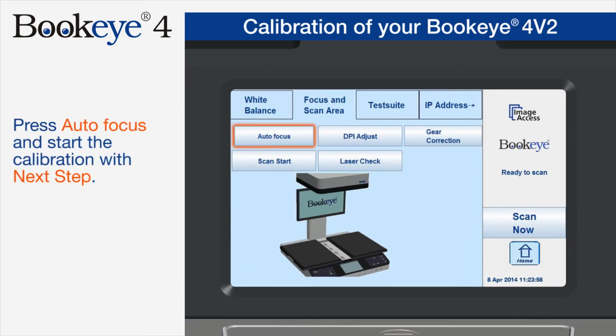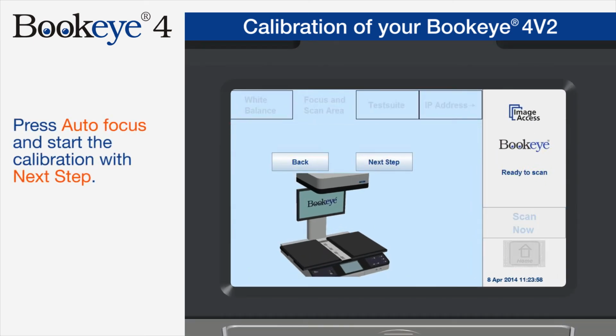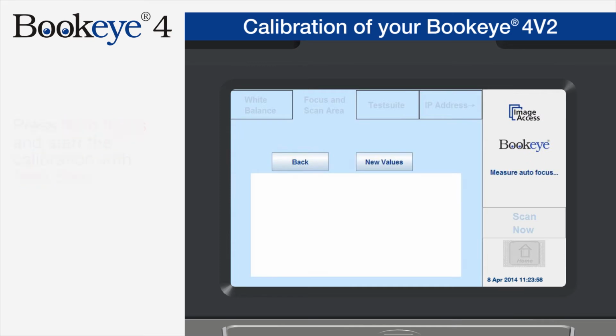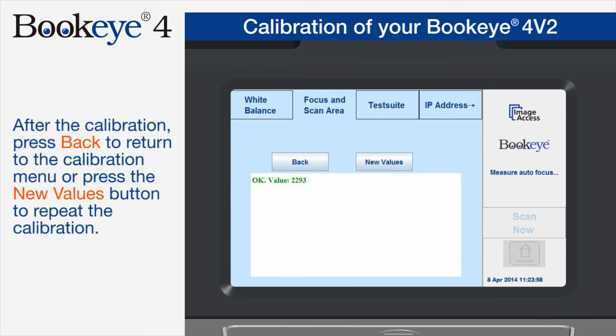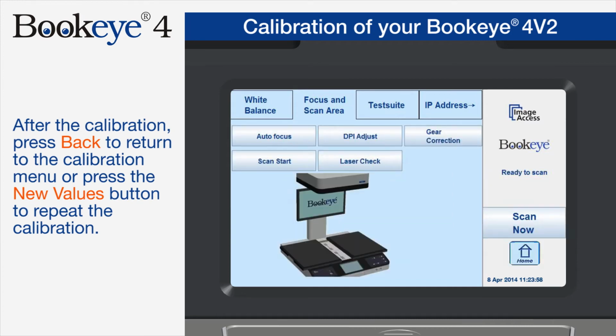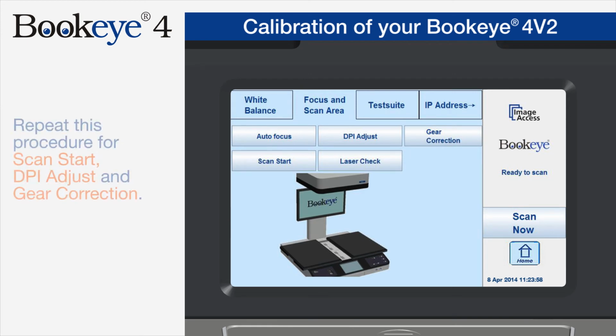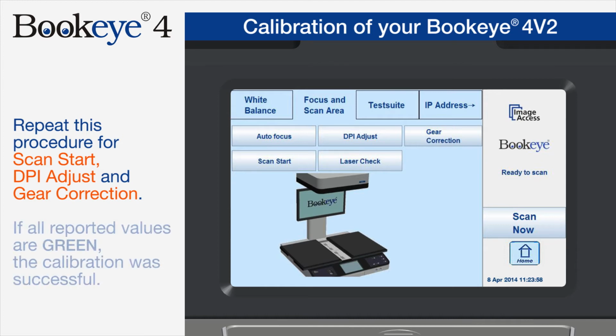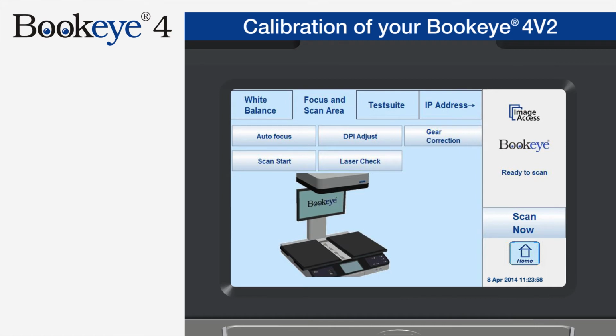Press the autofocus button and start the calibration by tapping the Next Step button. After the calibration, press the back button to return to the calibration menu, or press the New Values button to repeat the calibration. Repeat this procedure for Scan Start, DPI Adjust, and Gear Correction. If all reported values are green, the calibration was successful.